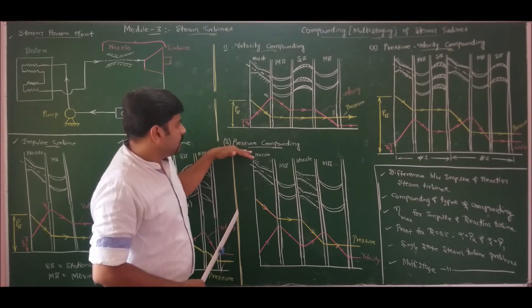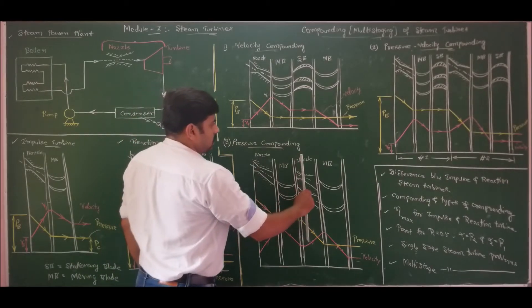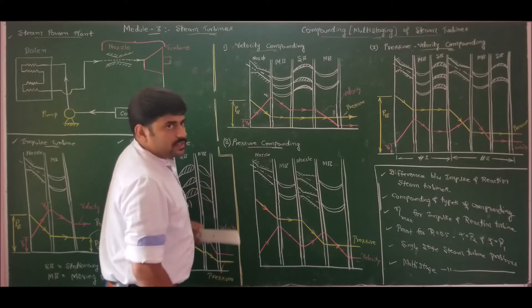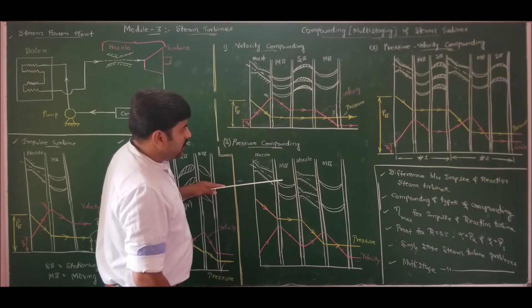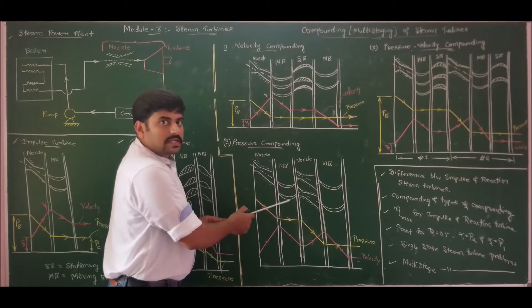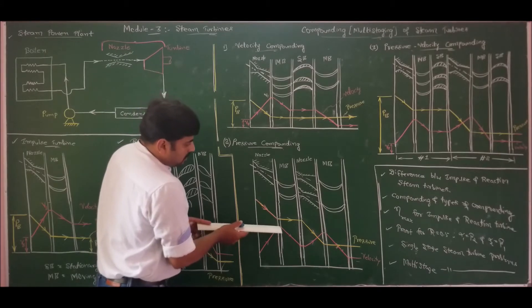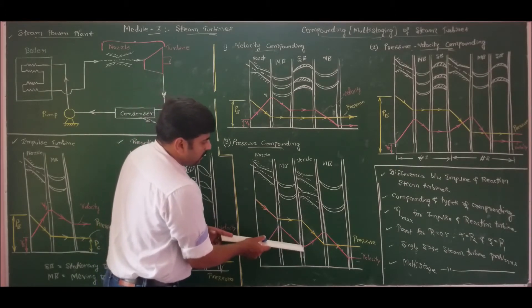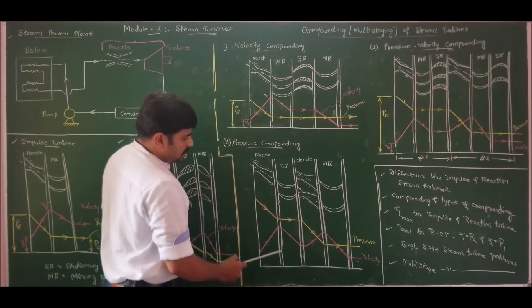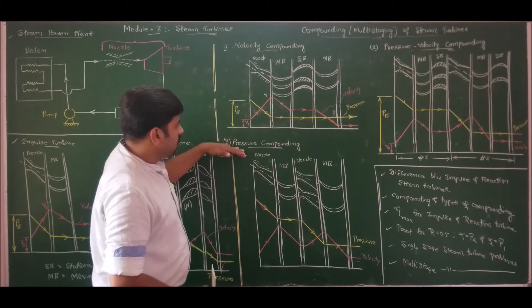For pressure compounding, the arrangement is: nozzle, moving blade, nozzle, moving blade — alternating rows of nozzles and moving blades. When steam passes through each nozzle, a pressure drop is observed and velocity increases. On the symmetric moving blades, pressure remains constant and velocity decreases. Then again in the next nozzle, velocity increases and pressure decreases, and in the moving blade, pressure remains constant and velocity decreases. In this way, we make maximum use of the kinetic energy in the steam — this is pressure compounded steam turbines.